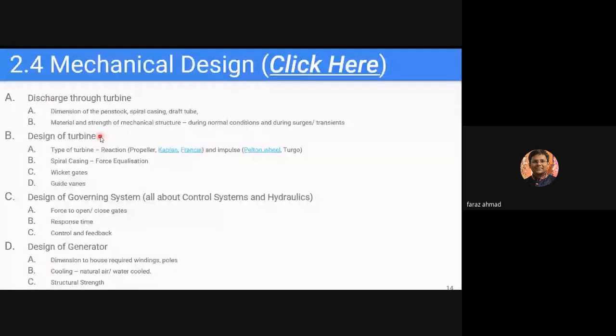So while designing a generator, you have a constraint on its RPM in the case of a power plant, because you have a constraint on the head of the plant, and then you have to design the penstocks and the discharge. So head and discharge are fixed. When discharge is fixed, the design of the turbine is fixed. When the design of the turbine is fixed, the rated RPM and the total output of the turbine are fixed for a given amount of force being converted from mechanical to electrical energy through generators. So you cannot have much variation in the dimensions of a machine, basically.